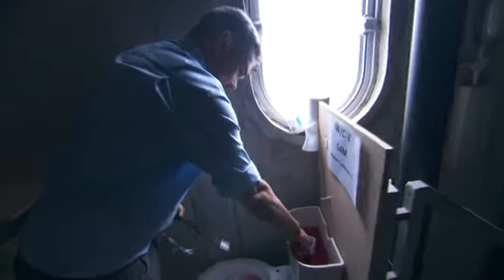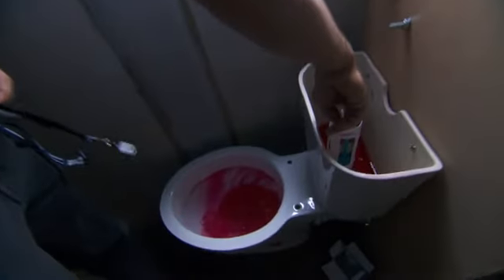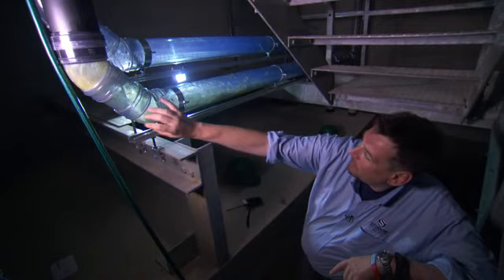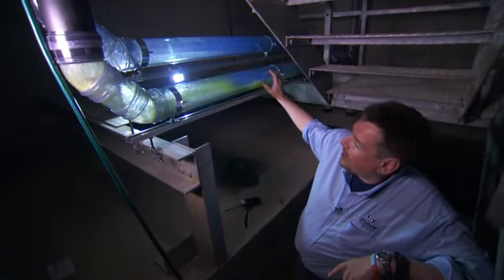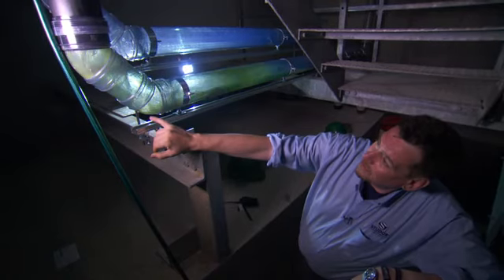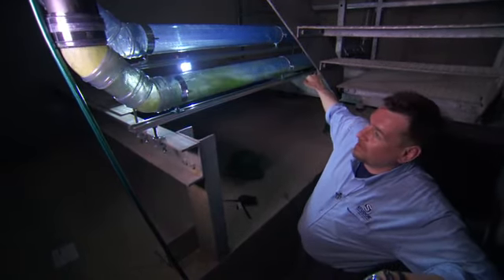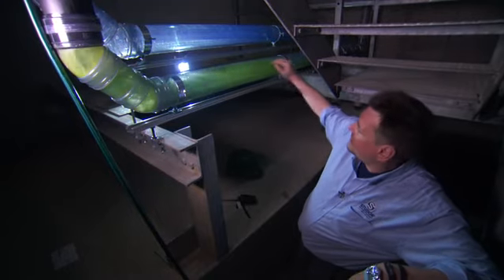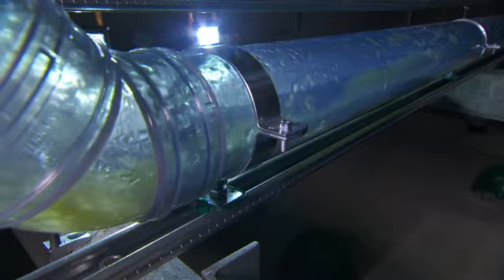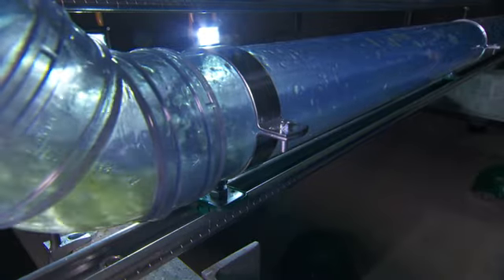Today they do a toilet paper flush. Flush in. You can see the toilet paper coming in and it obliterates itself, then the flow comes in from the flush afterwards. Tampons and wet wipes cause even bigger problems. You can hear the towel going off, hitting and oscillating. If these towels block the air traveling down for just 10 milliseconds, it blasts back up the stack at 320 meters a second.